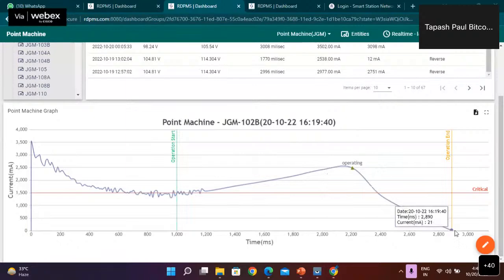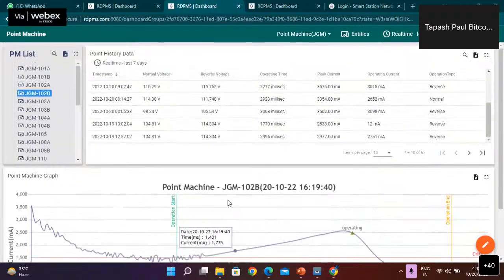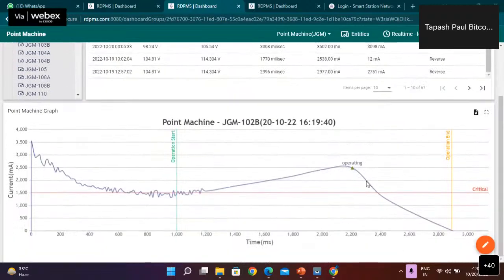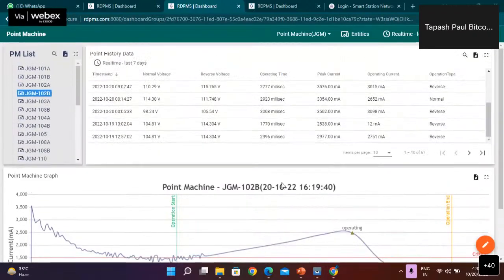2.4 ampere current was taken by the point machine, then it was set and locked at 2.8 second. If my operation time is more, the system will generate an alarm that the system is obstructed with some hard obstruction. If the obstruction time is only slightly deviating and operating current is more, the system will generate alarms related to drying and soft obstruction.